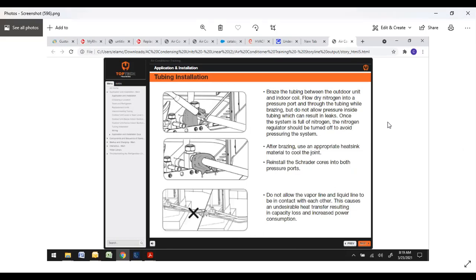Braze the tubing between the outdoor unit and indoor. Be sure to flow nitrogen into the lines as you're brazing. The purpose for that is to keep all that oxidization out of the inside of the line. All that black junk you see on the outside, if you don't flow nitrogen properly, all the black stuff, debris and scale you see on the outside will also be on the inside. And if you have 4 connections, 2 on the outside, 2 on the inside, that's a lot of little tiny debris that will be floating around in your system.